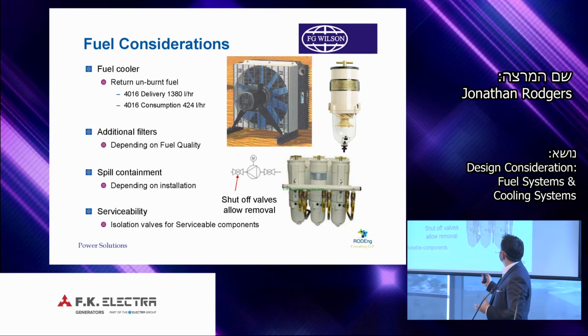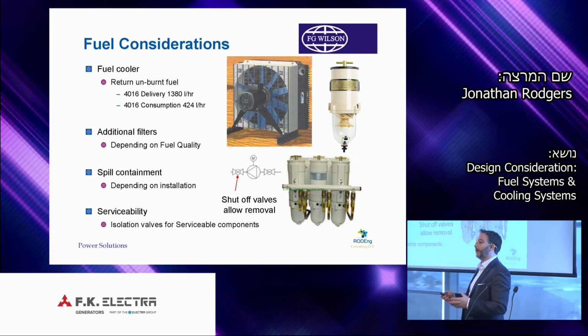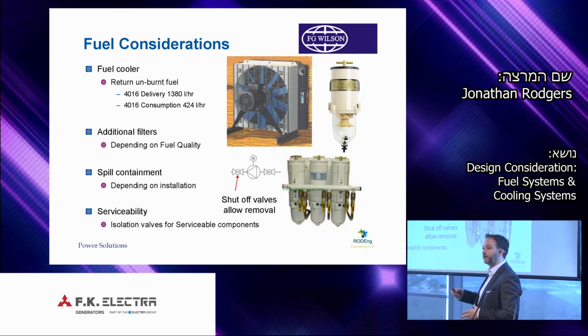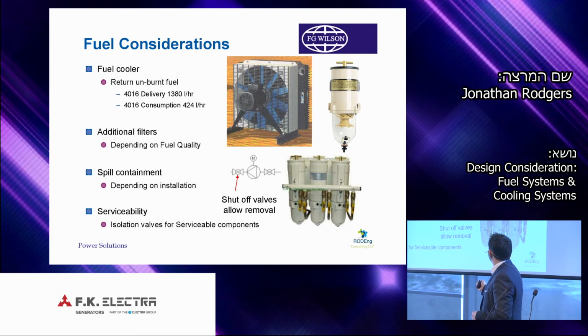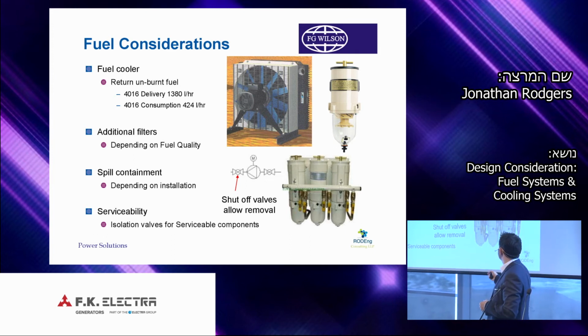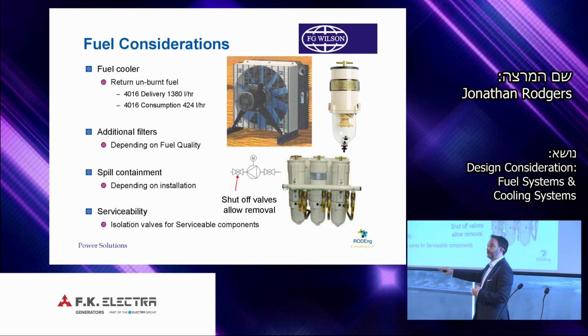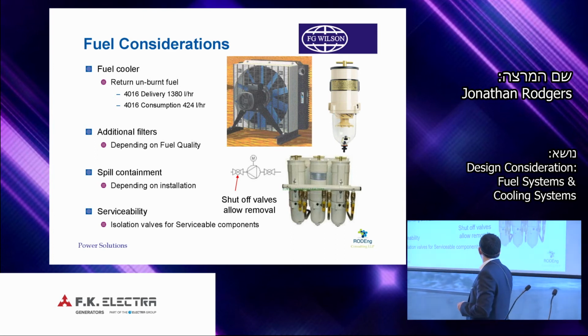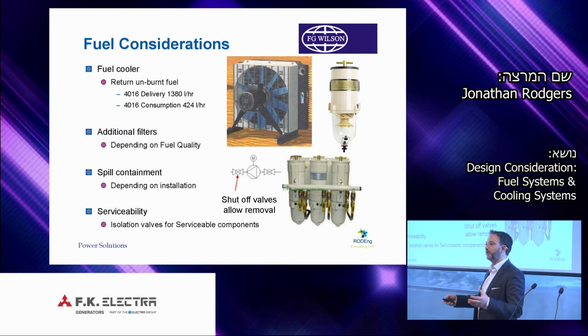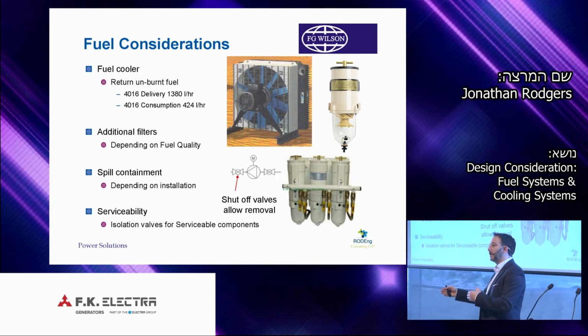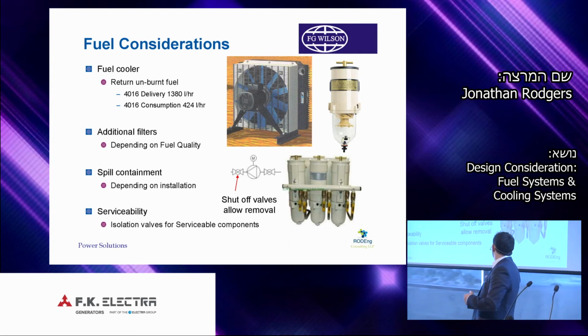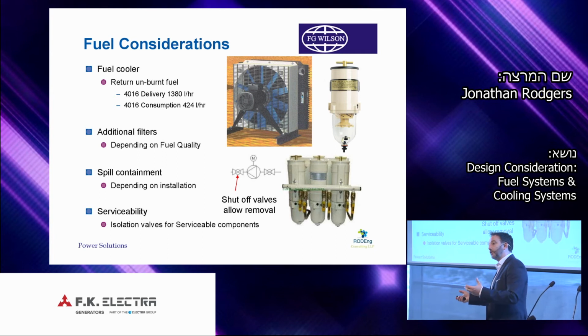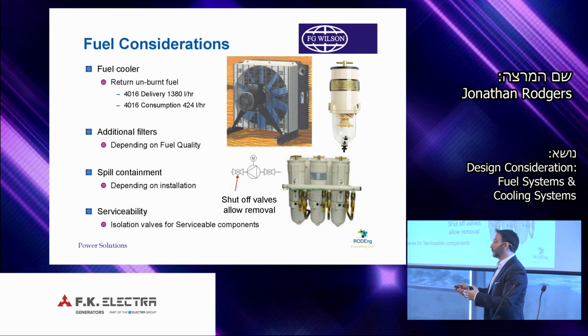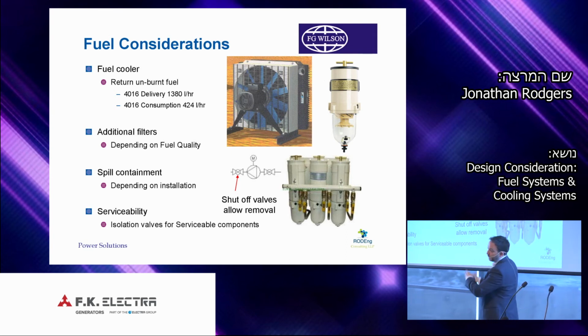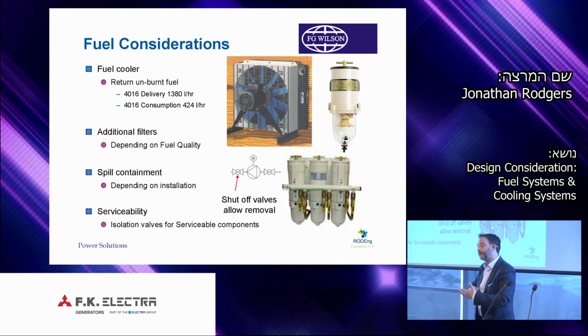We may, depending on location, depending on environment, have additional filters. We use a lot of these Racor type filters. They can be arranged in duty standby configurations where you can remove one element while the engine is continuing to run. We use these in a lot of United Nations and military applications where there are prime rated generators or base load generators, and if there's contamination or the fuel filters need to be changed while the engine is running, we can isolate one filter element, remove it, and keep the flow through the other filters. So it keeps it running continuously.